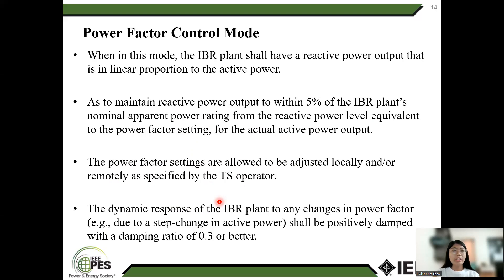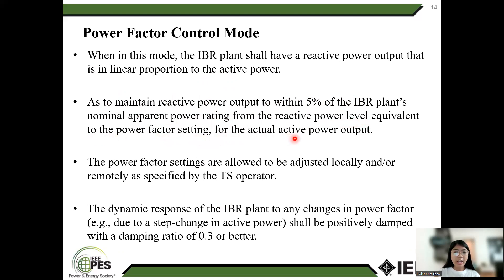Power factor control mode. In this mode, the IBR plant should have a reactive power output that is in a linear relationship to the active power, to maintain a reactive power output within 5% of the IBR plant's nominated apparent power rating from the reactive power level equivalent to the power factor setting for the actual active power output. The power factor settings are allowed to be adjusted locally or remotely as specified by the TSO. The dynamic response of the IBR plant to any changes in power factor shall be positively damped with a damping ratio of 0.3 or better.